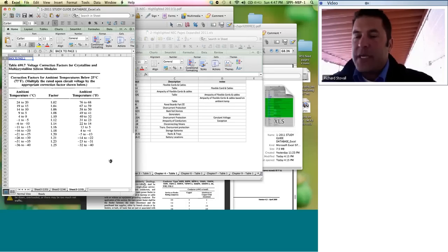Bill Brooks, he's a genius PV guy. His perspective is probably true, that if you were using monocrystalline or polycrystalline and you utilize that table, it's conservative and you'd be okay. You're still going to need to do temperature calculations on the low voltage side anyway, utilizing temperature coefficients, so you might as well have accurate numbers.